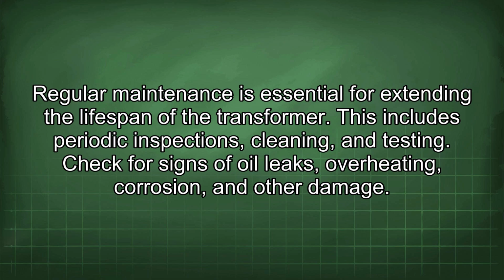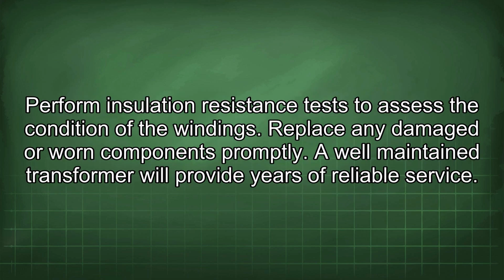Regular maintenance is essential for extending the lifespan of the transformer. This includes periodic inspections, cleaning, and testing. Check for signs of oil leaks, overheating, corrosion, and other damage. Perform insulation resistance tests to assess the condition of the windings. Replace any damaged or worn components promptly. A well-maintained transformer will provide years of reliable service.